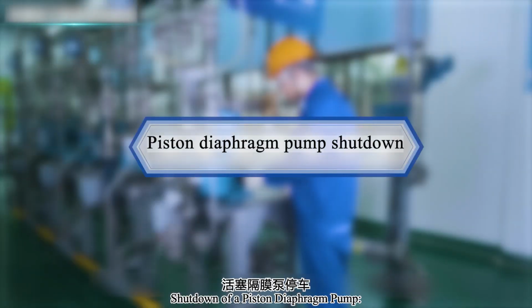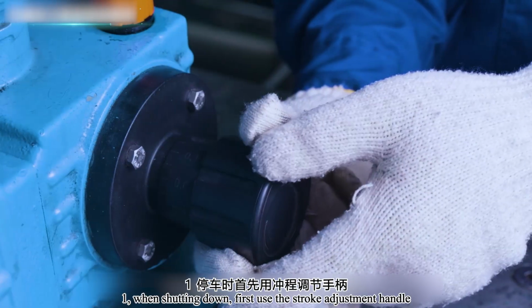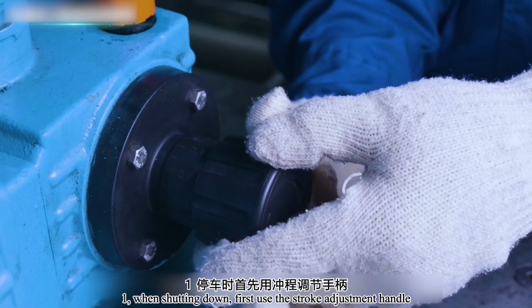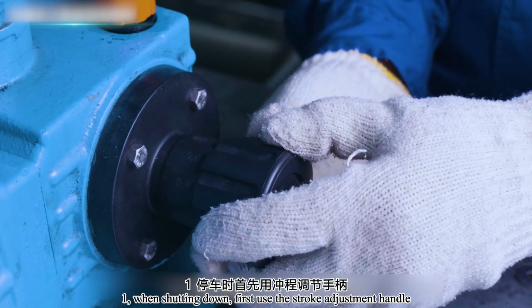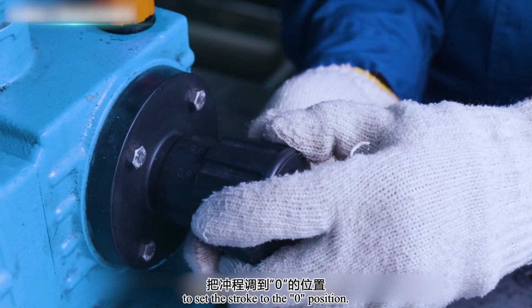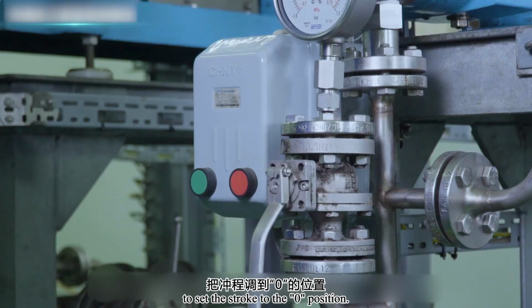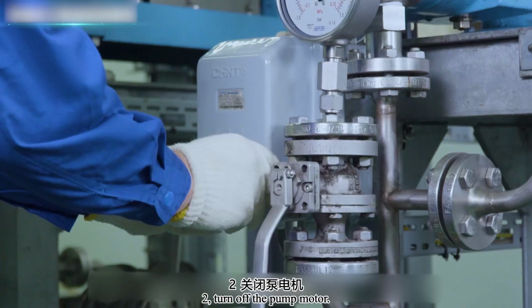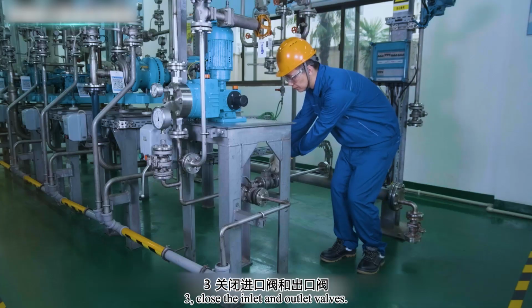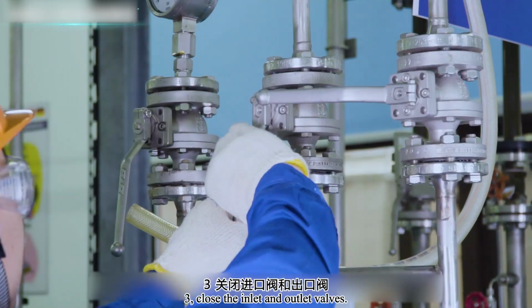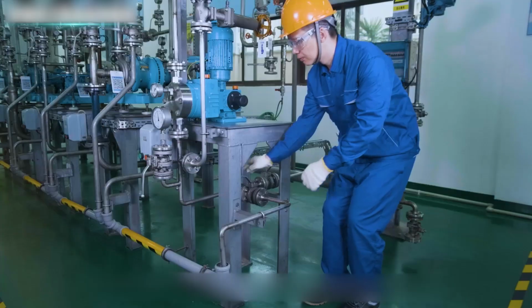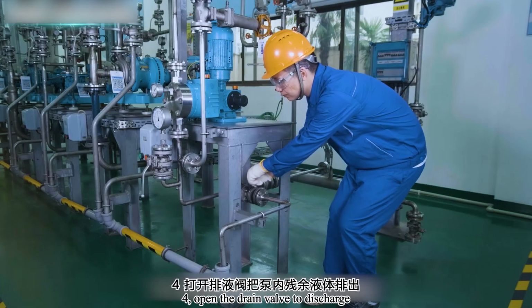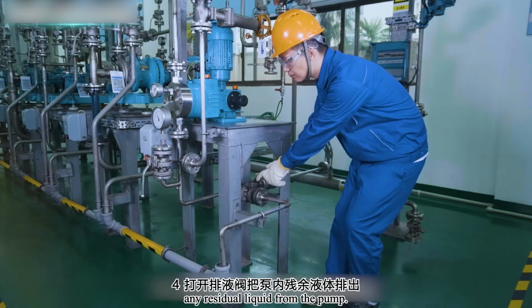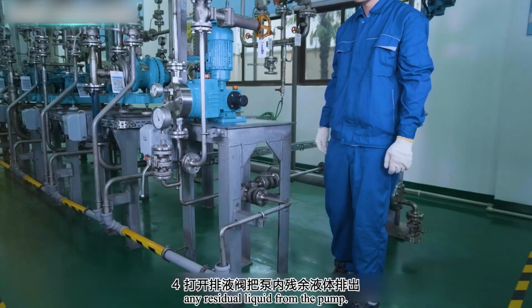Shutdown of a piston diaphragm pump. First, when shutting down, first use the stroke adjustment handle to set the stroke to the 0 position. Second, turn off the pump motor. Third, close the inlet and outlet valves. Fourth, open the drain valve to discharge any residual liquid from the pump.